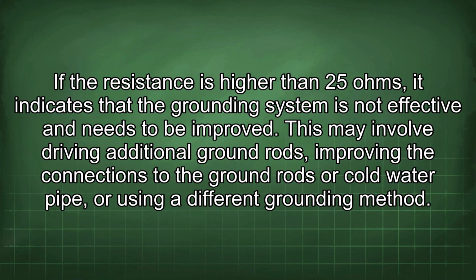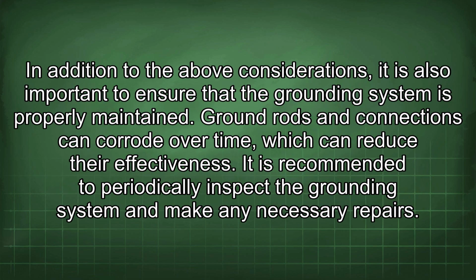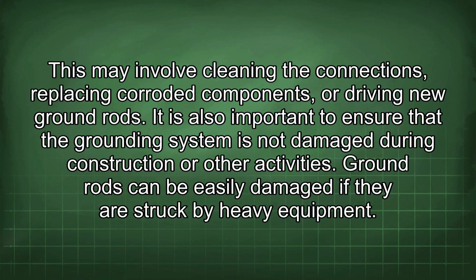If the resistance is higher than 25 ohms, it indicates that the grounding system is not effective and needs to be improved. This may involve driving additional ground rods, improving the connections to the ground rods or cold water pipe, or using a different grounding method. In addition to the above considerations, it is also important to ensure that the grounding system is properly maintained. Ground rods and connections can corrode over time, which can reduce their effectiveness. It is recommended to periodically inspect the grounding system and make any necessary repairs. This may involve cleaning the connections, replacing corroded components, or driving new ground rods.